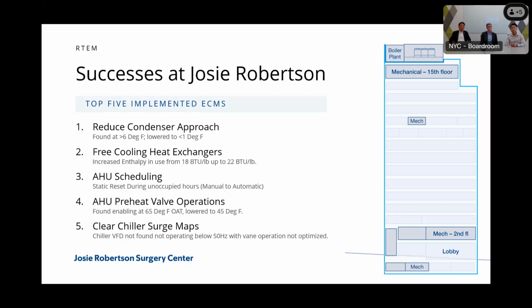We also implemented some setbacks for air handlers for unoccupied times and for night setbacks. We found some of our preheat valve operations not set properly, and we made those adjustments to reduce simultaneous heating and cooling. And one of our most important ones was that we cleared our chiller surge maps, because the way we were operating initially, we had implemented a lot of protections on the chiller. So once we were able to operate a little more efficiently, having those cleared out increased that efficiency even more.